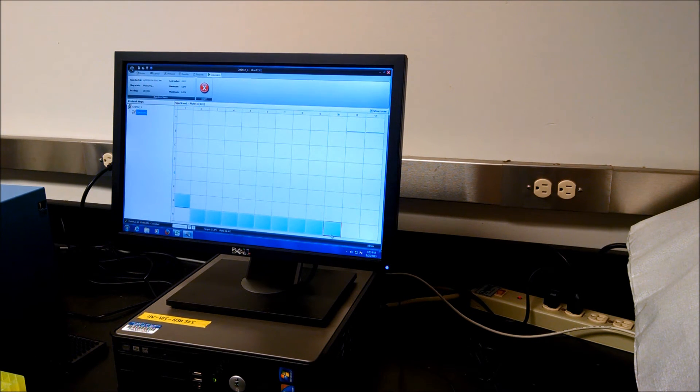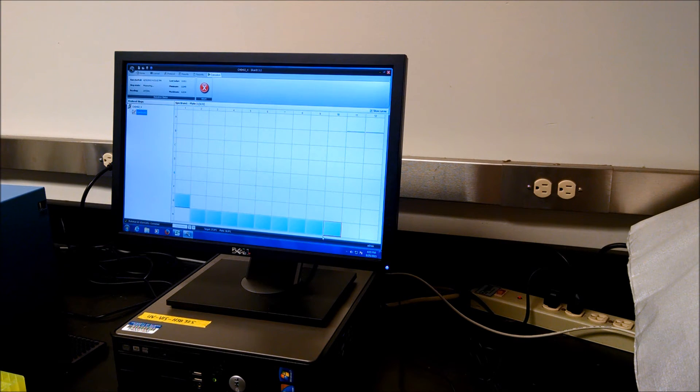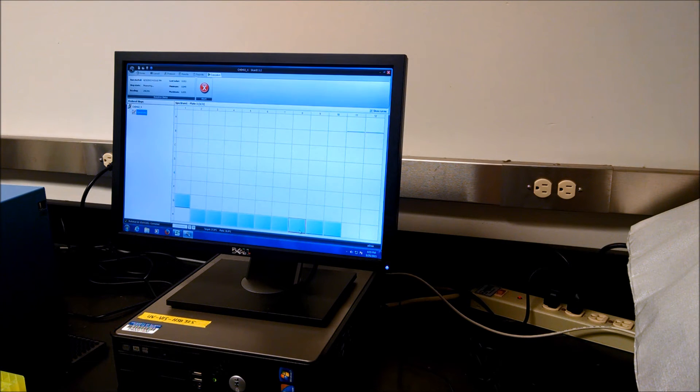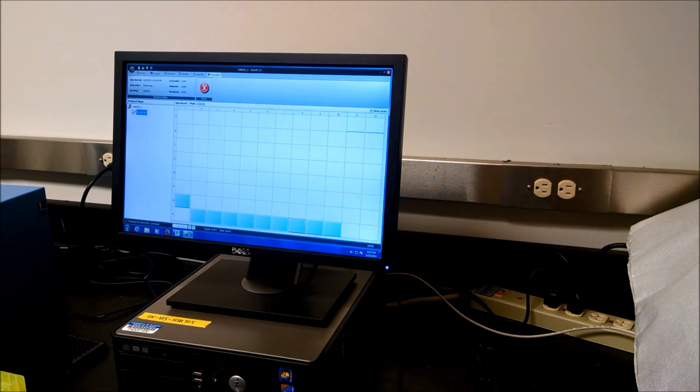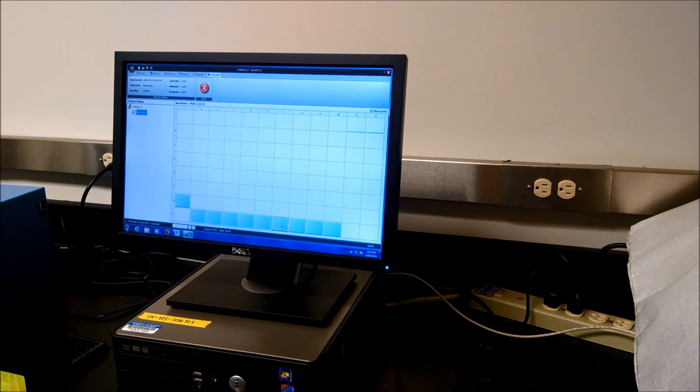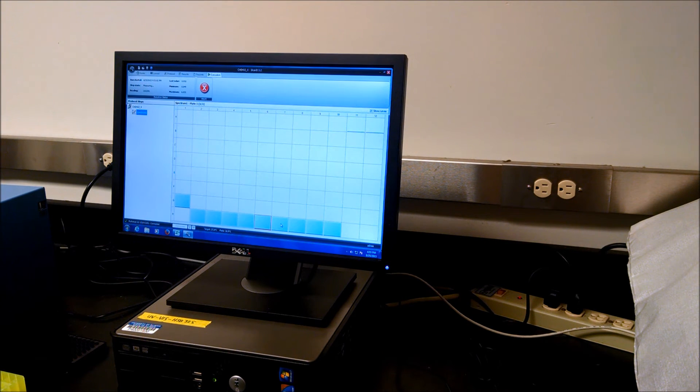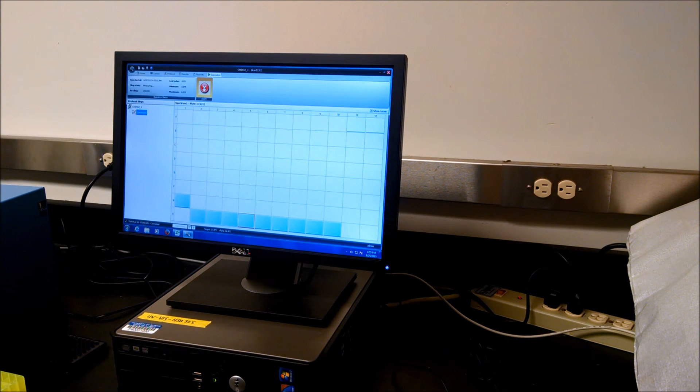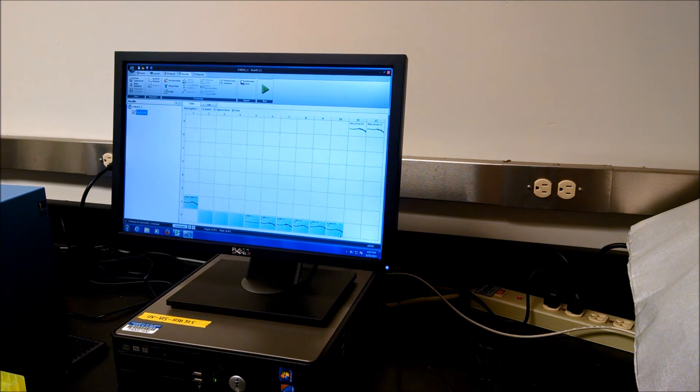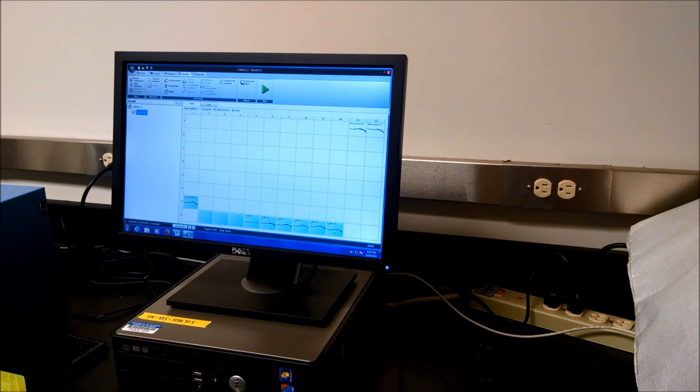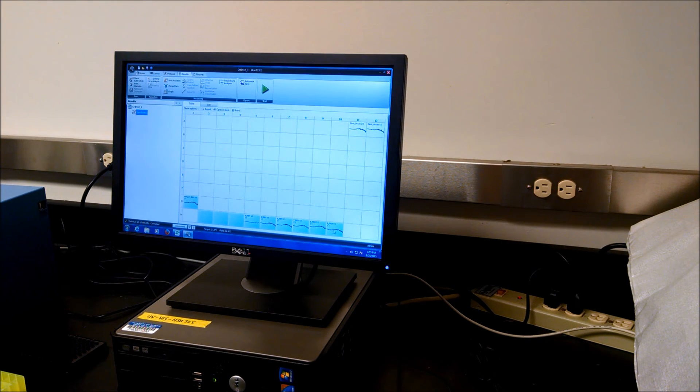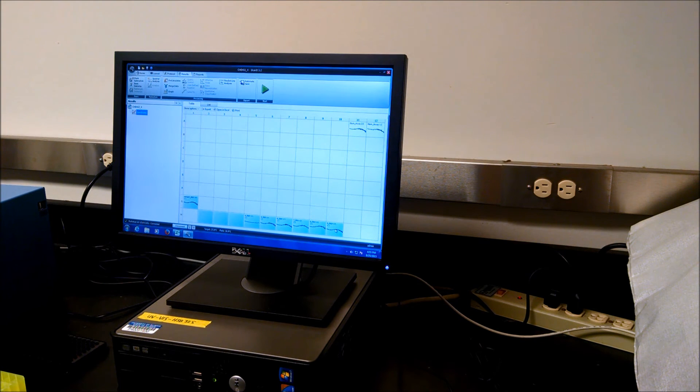And what you can't see, because there's nothing in those wells for our demonstration, is there's a line being drawn at the bottom of each cell here, which is the actual spectrum for the sample in that well. We don't need to do all of them just for this demonstration, but here now you can see I stopped it. Here you can see in each cell is the actual scan, the spectrum, for the sample that was in that well.